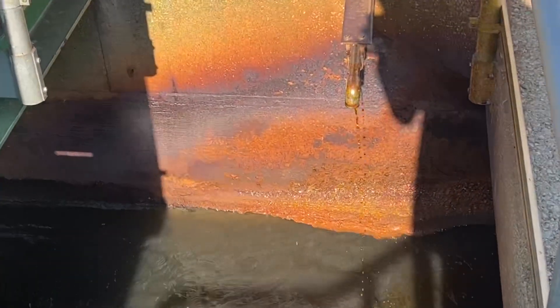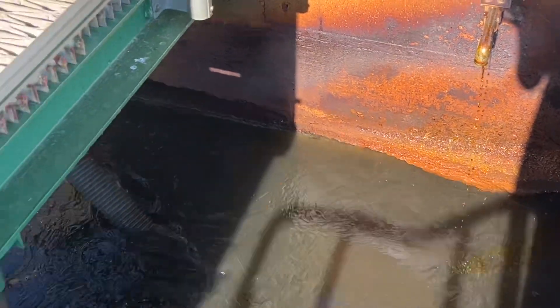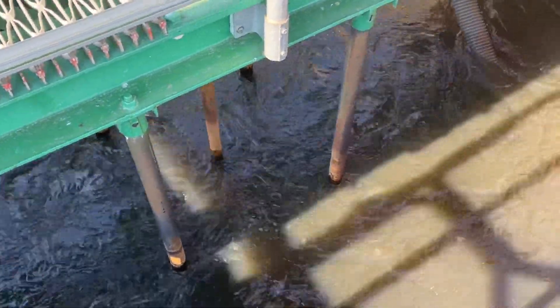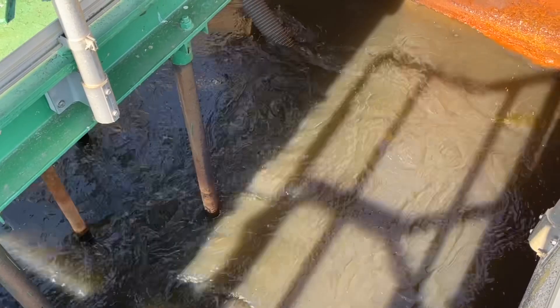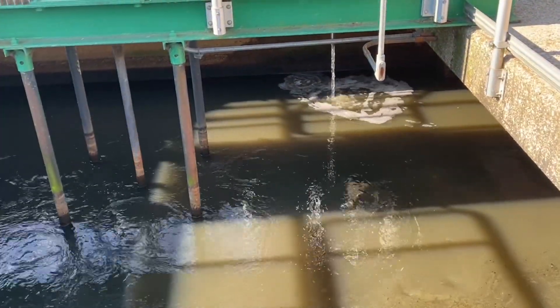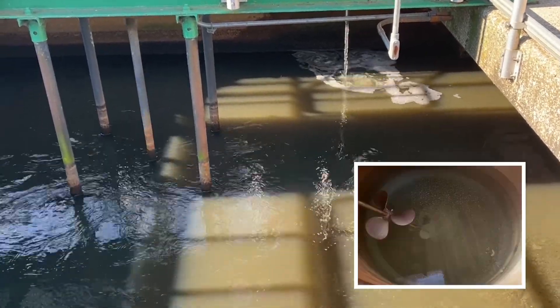As the water enters this tank, ferric chloride and acid is added to the water. There is a mixer that flash mixes the entire tank to distribute the ferric chloride, which bonds with the phosphate ions to create a heavier particle. As the water moves through these tanks, we then add polymer to take the coagulated particles and flocculate them into larger particles that will better settle out in a clarifier.